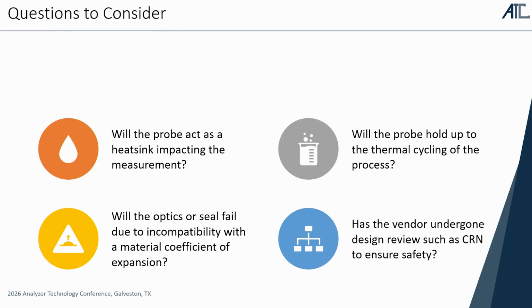If you're in a reactor and you're doing a wash at the end and you're putting 80 degree xylene into a 230 degree polyurethane reactor as a wash, is that thermal shock going to kill the probe? So some of these kinds of maintenance, serviceability, and lifetime things are often overlooked.